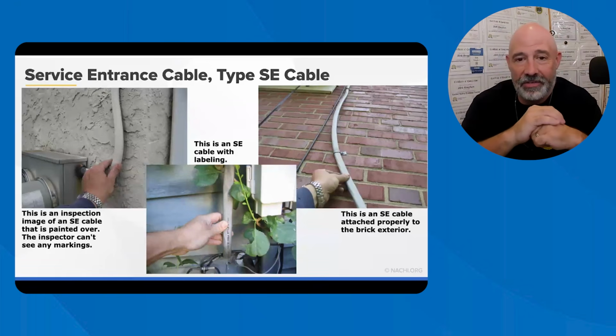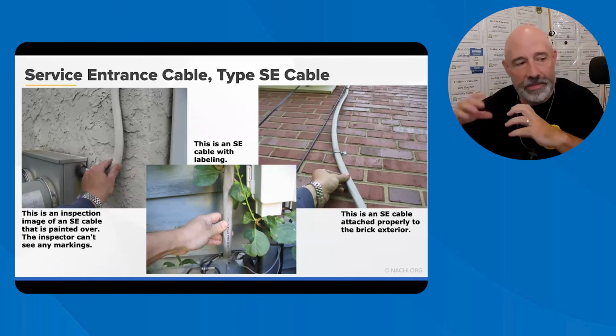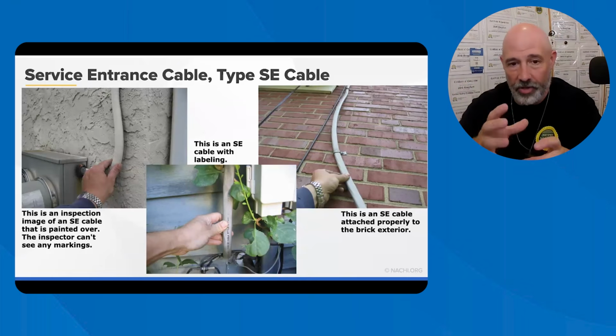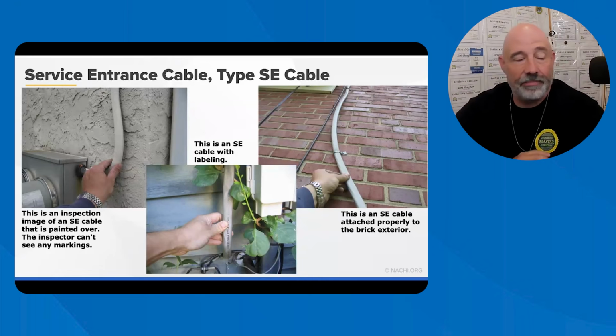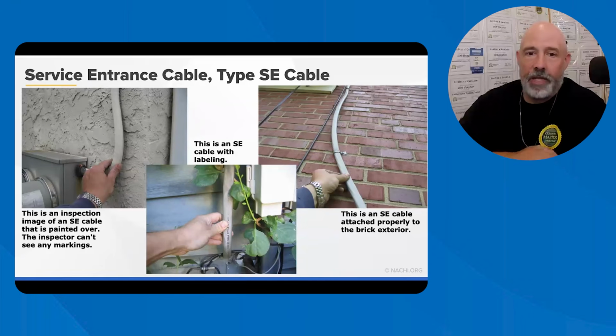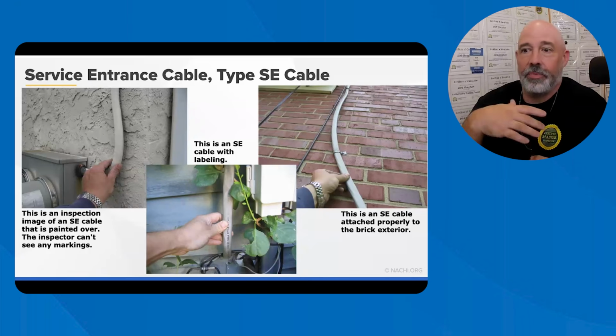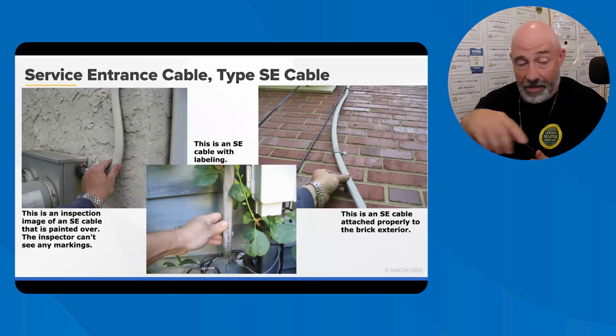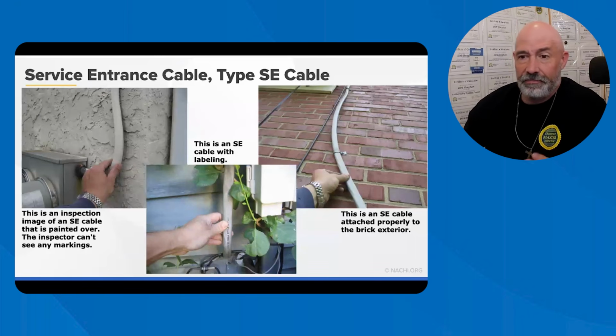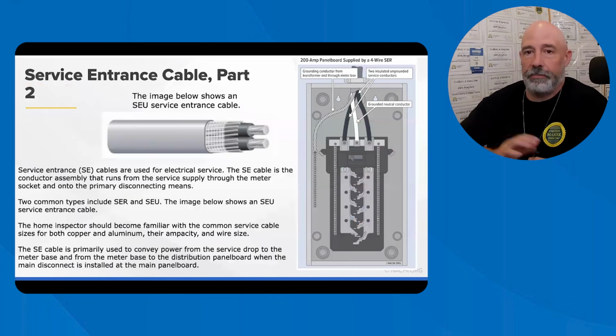because you want to make sure that everything is nice and solid and connected together. I kind of think of it like your body, all one unit. Same thing, you want it all to be connected into one unit and make sure that it's sealed so that, you know, bugs and pests and rain can't get in there. So the cable should be attached to the building every 30 inches along its length and within a foot of the top of the meter can. So make sure that you check that. And you can eyeball it. I mean, it's not like, if it's 30.5 inches, oh, I'm going to call this out. Don't be that big of a stickler on it.